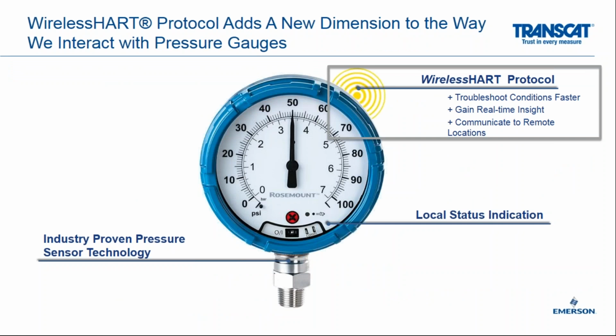And then finally, we'll talk about wireless. I mentioned I'd leave this to the end. Up until now, what you may see is that this gauge is a more reliable gauge than a Bourdon tube style gauge for many different reasons. There's a secondary piece of this gauge that really makes it even more reliable, and that's WirelessHART protocol. The WirelessHART protocol allows you to take that information that would be otherwise stranded in this gauge and communicate that elsewhere. It can help you troubleshoot faster, helps you gain a lot of real-time insights, and then you can communicate with these gauges remotely.